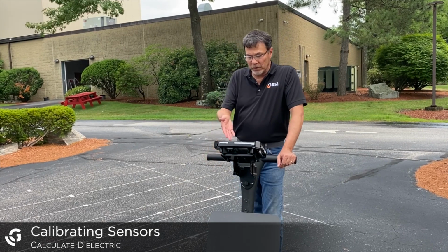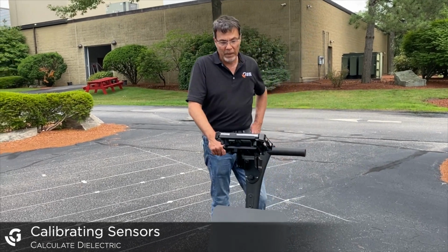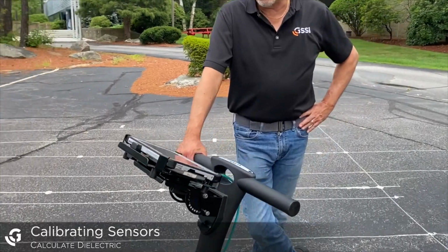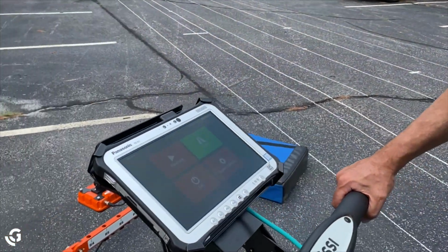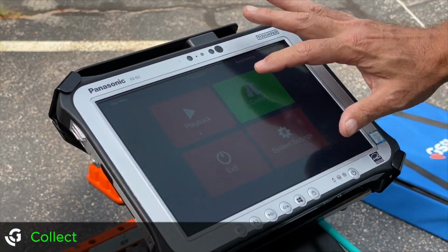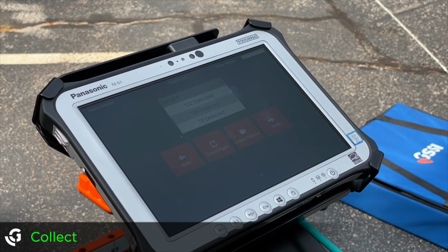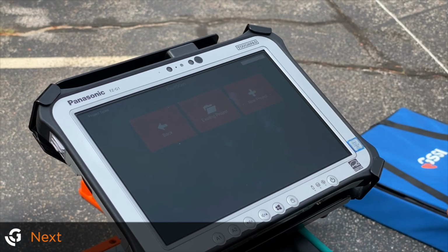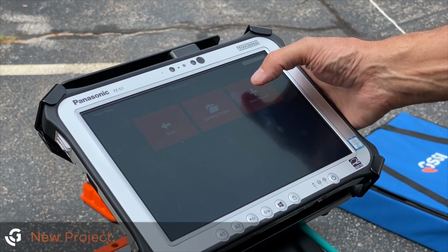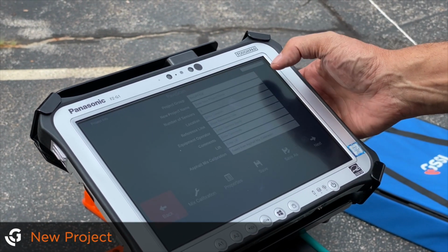It requires an air calibration and a metal plate calibration, which we'll go through now. We're going to show you the main menu and the steps needed. I'm going to collect data on site, but it will require calibration. It found all three of my sensors here, so I'm going to create a new project.